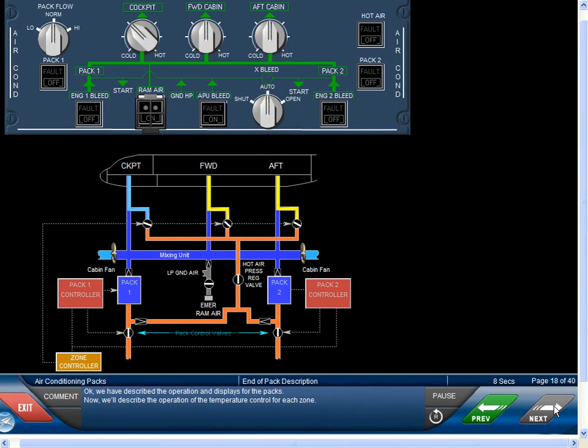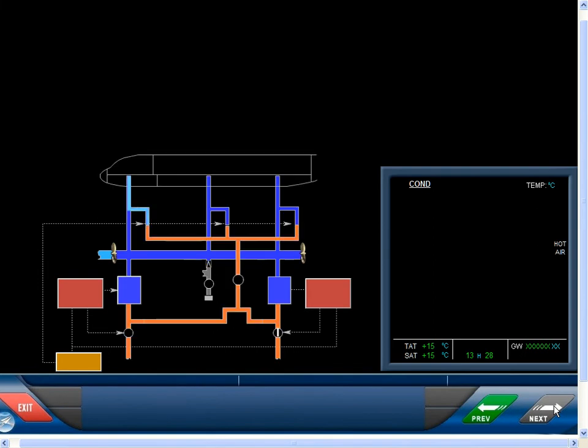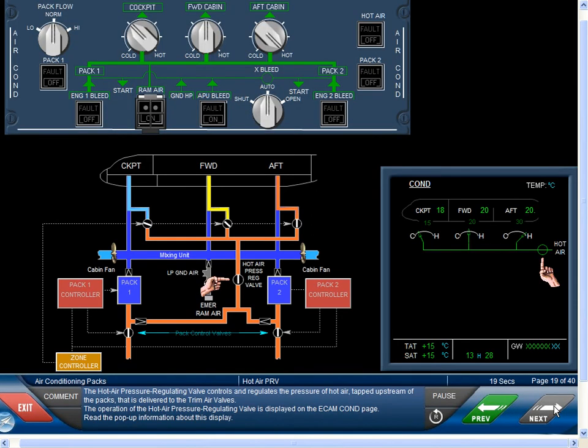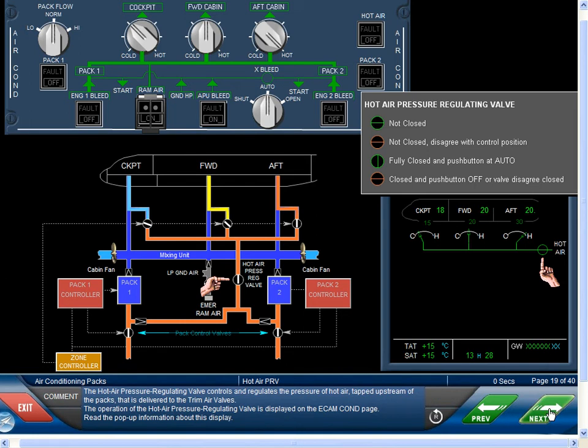Okay, we have described the operation and displays for the packs. Now we'll describe the operation of the temperature control for each zone. The hot air pressure regulating valve controls and regulates the pressure of hot air tapped upstream of the packs that is delivered to the trim air valves. The operation of the hot air pressure regulating valve is displayed on the ECAM condition page. Read the pop-up information about this display.